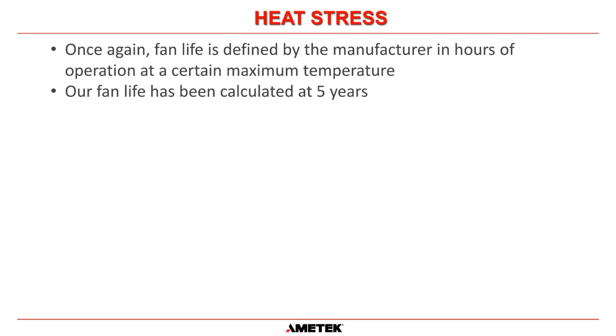And also we've got to pay attention to our fan life. And once again, that is determined by the manufacturer of our fans, and they tell us how many hours to expect for certain temperatures. And we extrapolated that data, and it says our fan life has been calculated at about 5 years within the temperature tolerance of our UPS, which is up to an operating temperature of 105 degrees Fahrenheit. So you should get 5 years life out of your fan as long as your UPS internal temperature is 105 degrees Fahrenheit or less.